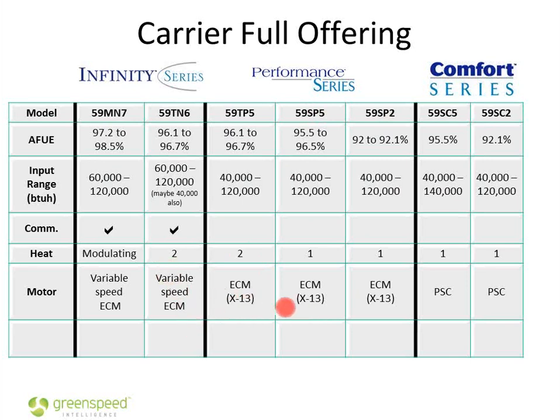The regular X13 ECM motor, it's an ECM motor, so it's a DC motor, which is fairly efficient, and we can dictate to it a couple different speeds. I think that motor has 5 different speeds, and we typically use 3 of them with a furnace. We'll tell it, go to this particular speed for first stage heat, first stage cooling, or just recirc mode. Go to this other higher speed for cooling, and go to this other higher speed for two-stage heating.